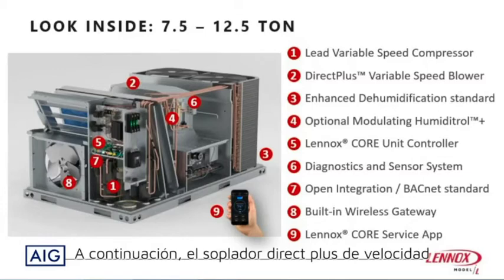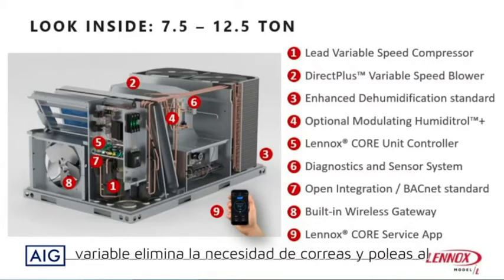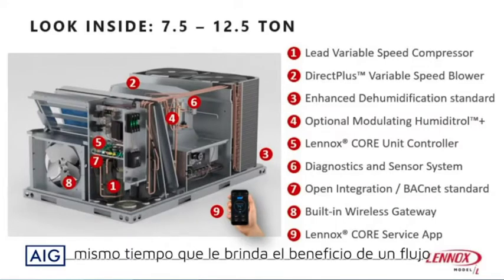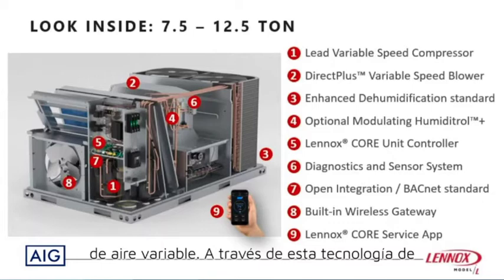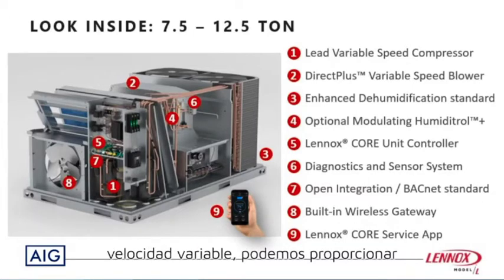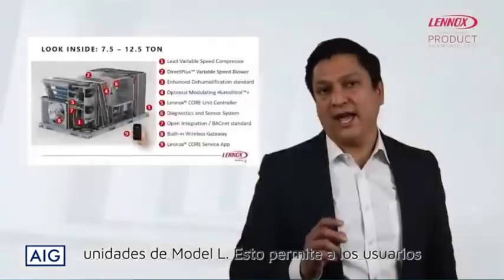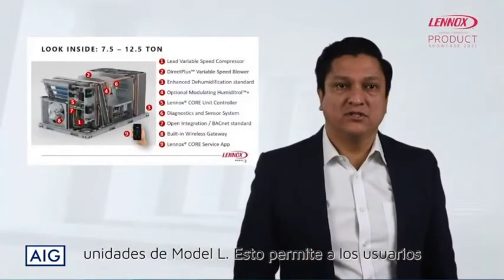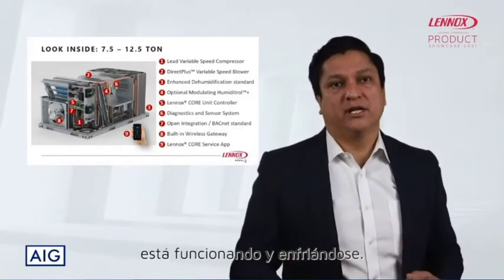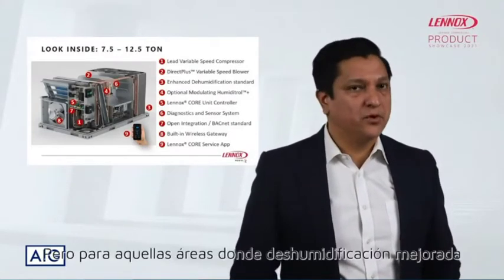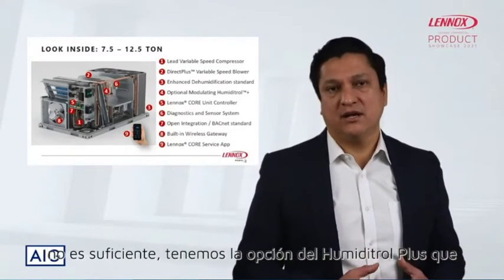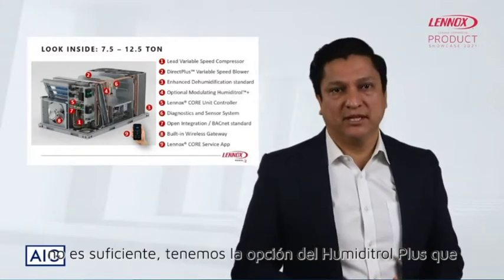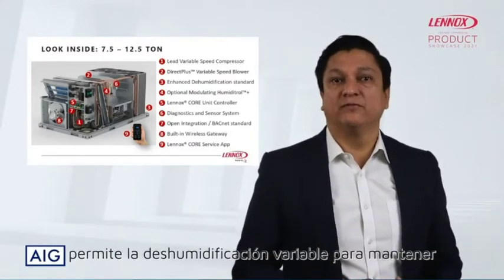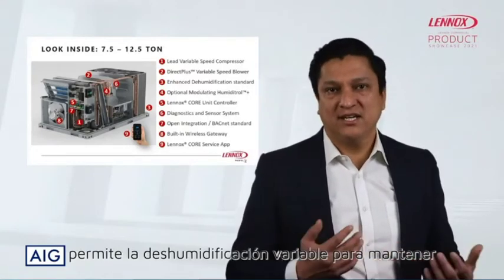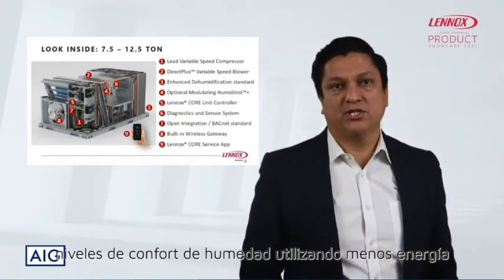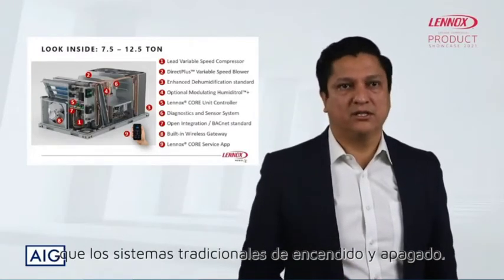Next, the direct plus variable speed blower eliminates the need for belts and pulleys while giving you the benefit of variable airflow. Through this variable speed technology, we're able to provide standard with all Model L units enhanced dehumidification. This allows users to remove some moisture while the unit is running in cooling operation. But for those areas where enhanced dehumidification is not enough, we have the optional Humiditrol Plus. Humiditrol Plus allows variable dehumidification to maintain comfortable humidity levels using less energy than traditional on and off dehumidification systems.